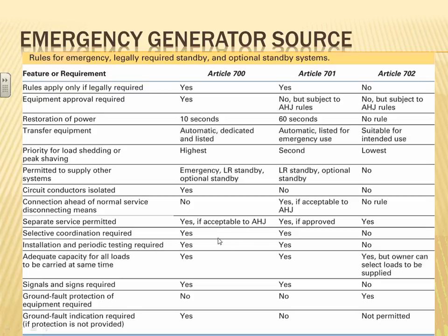Selective coordination, you have to do selective coordination for the emergency and legally required standby systems, not for the optional. Installation and periodic testing, all of them have to be tested. Obviously, the optional, of course, optional. If you want to test it, you test it, it's up to you, but these must be tested. Capacity, they have to be able to carry the load.